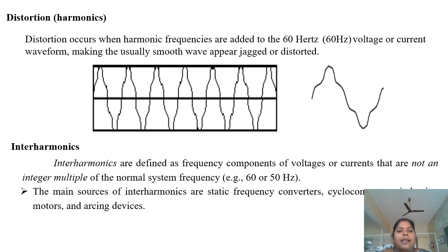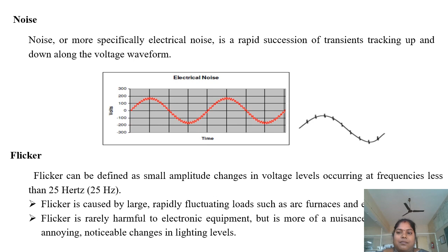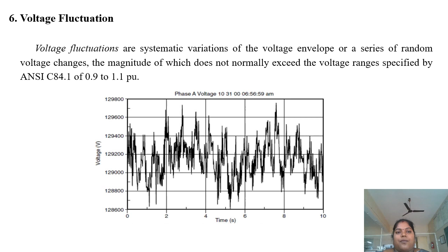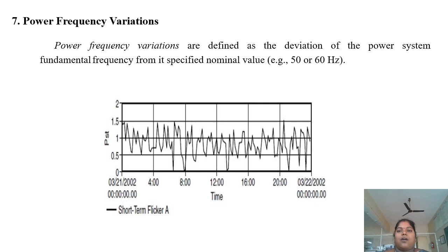Next one, flicker. It is defined as small amplitude changes in voltage levels occurring at a frequency of less than 25 Hz. Voltage fluctuations are systematic variations of the voltage envelope or a series of random voltage changes, the magnitude of which does not normally exceed the voltage range specified by ANSI C84.1 of 0.9 to 1.1 per unit. Power frequency variation, the next one, is defined as deviations of the power system fundamental frequency from its specified nominal value.